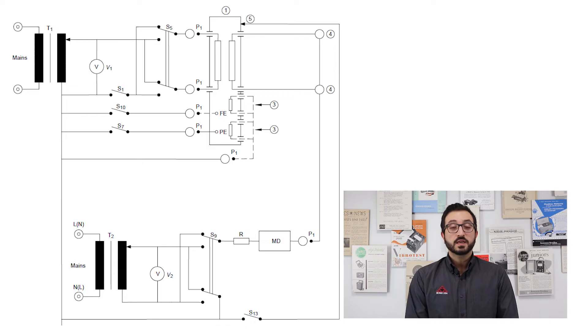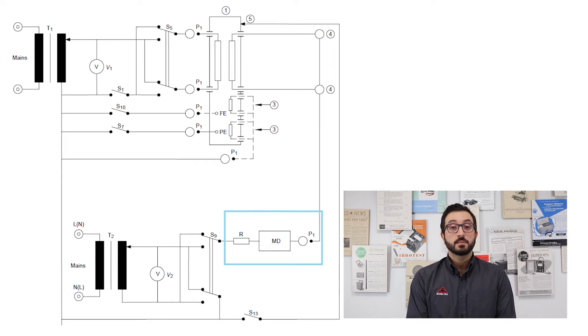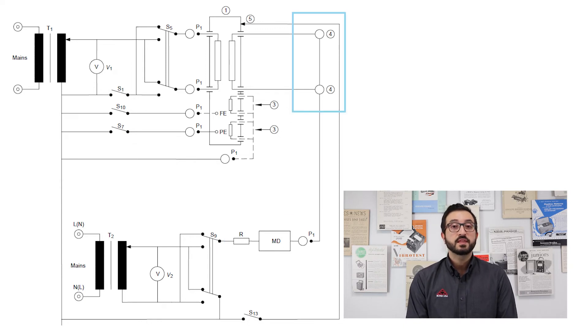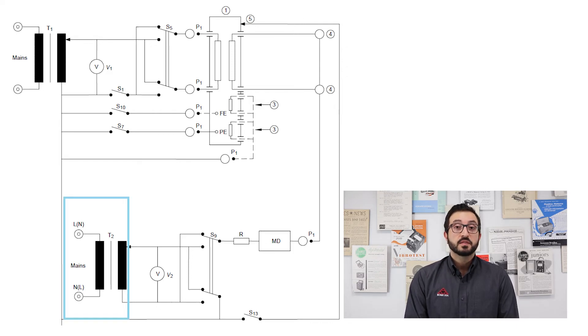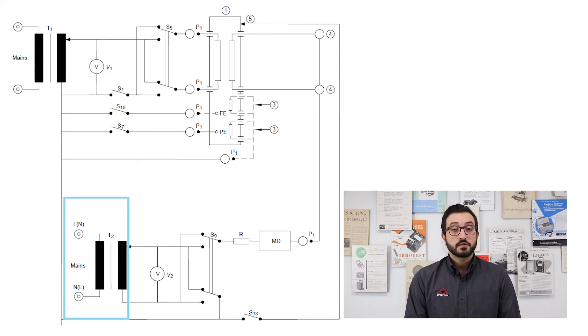Let's now take a look at how the mains and applied part leakage current test is set up and performed according to the IEC 60601-1 medical device standard. The measuring device circuit simulating the human body impedance is placed between the applied parts, labeled as number 4 on the diagram, and the line of a secondary transformer labeled T2.